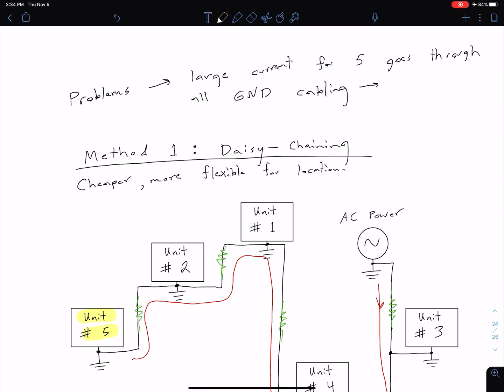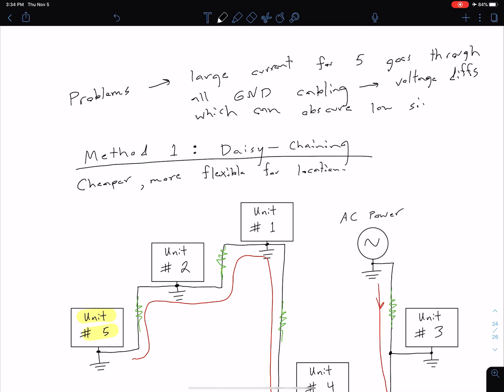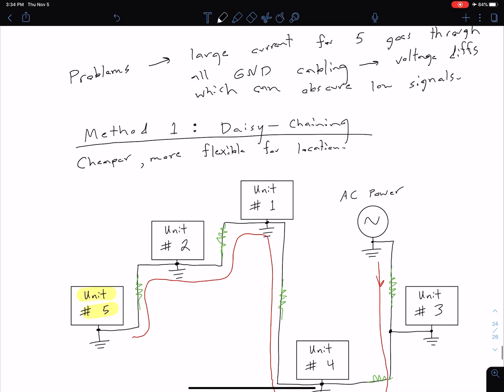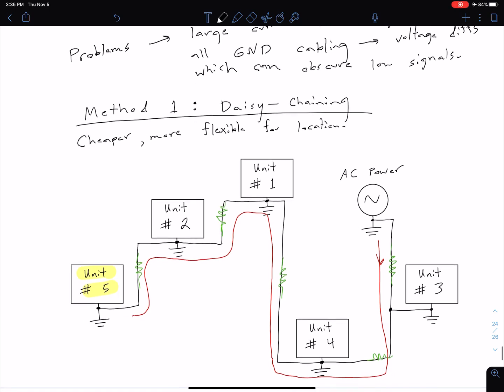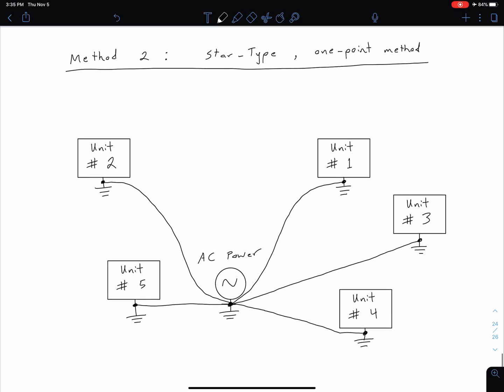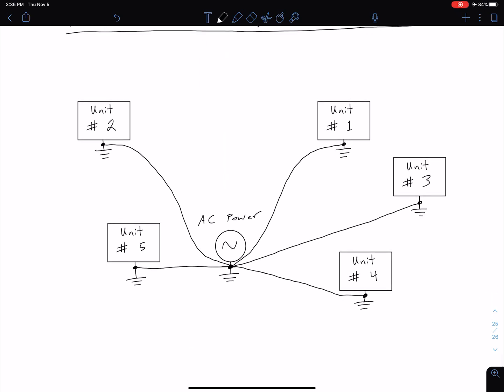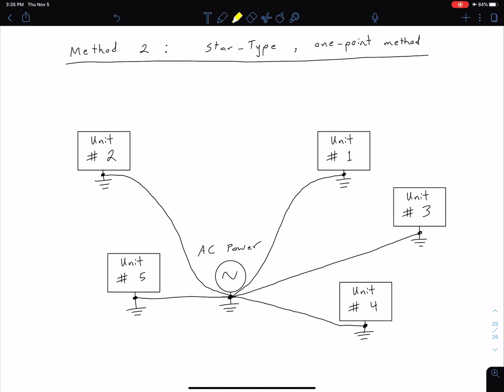This is a similar idea to what we talked about with the camera example. But remember, daisy chaining does have the advantage of being cheaper and more flexible. The second method is the star type or one-point method. In this case, each of the five units is connected directly to the ground of the AC power source, rather than going through one unit to the next. The disadvantage is less flexibility in unit placement and potentially more cabling, but the advantage is a much lower risk for ground loops.